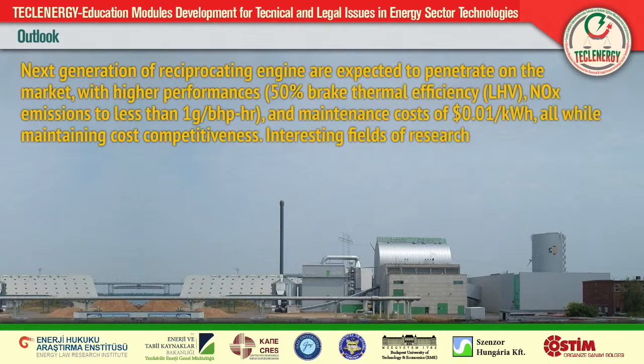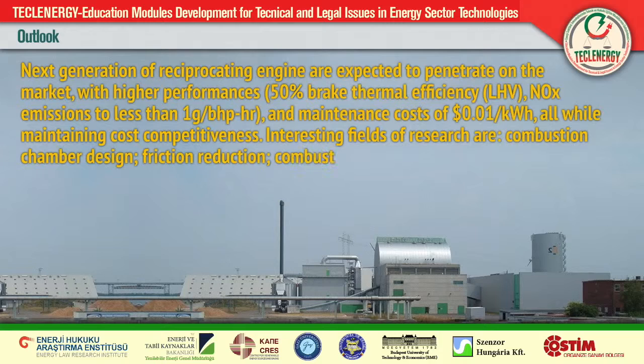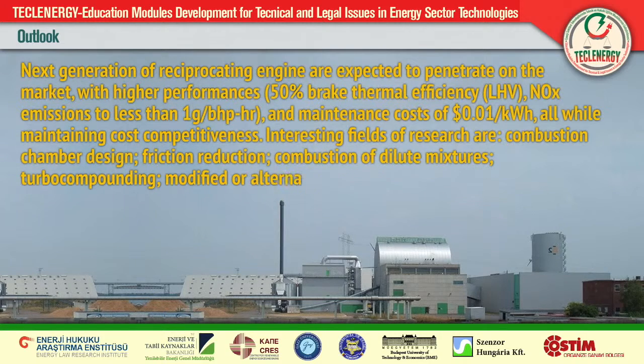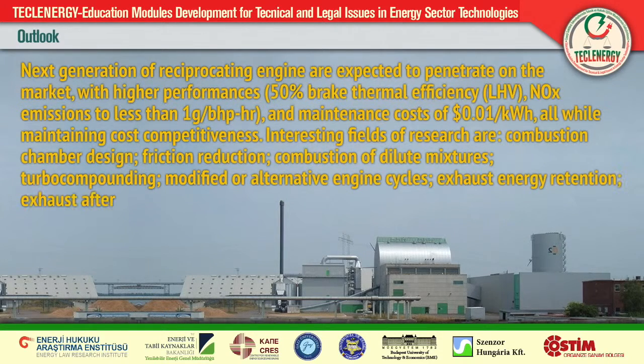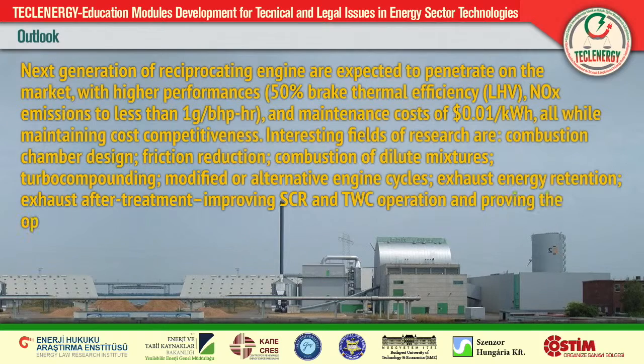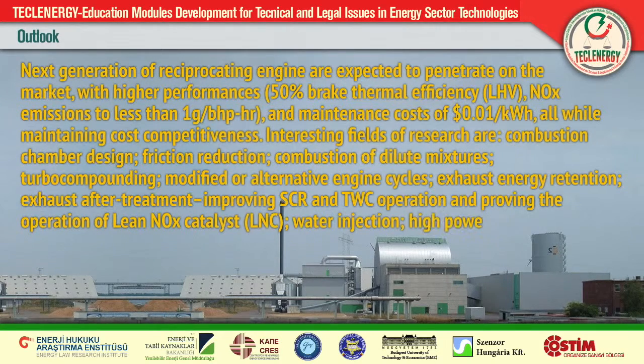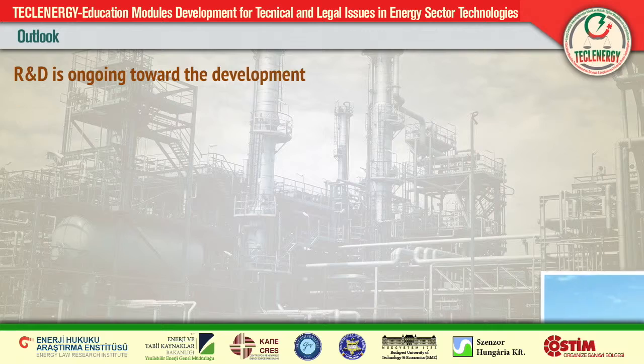The next generation of reciprocating engines is expected to penetrate the market with higher performance: 50% brake thermal efficiency LHV, NOx emissions of less than 1 gram/bhp per hour, and maintenance cost of 0.01 per kilowatt-hour, all while maintaining cost competitiveness.